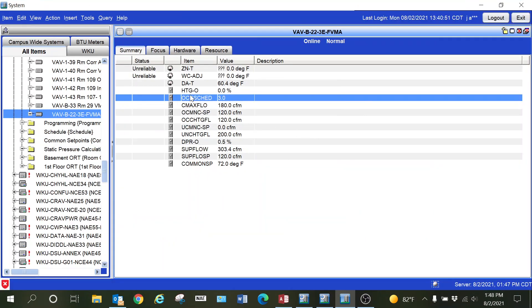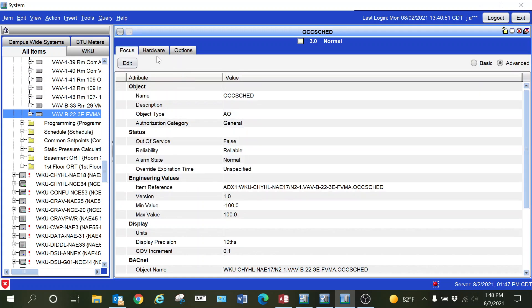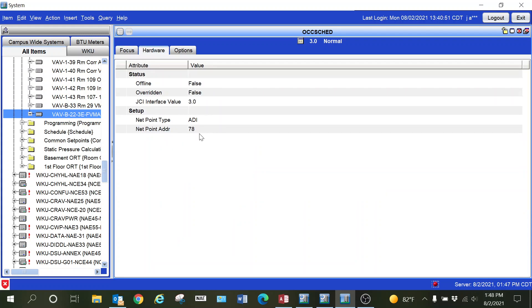In this video, I'm going to show you how to fix a point that has been pulled in incorrectly. You can see here the occupancy schedule point has come in as an analog value. One thing you want to do is look to see exactly what type of point this is.